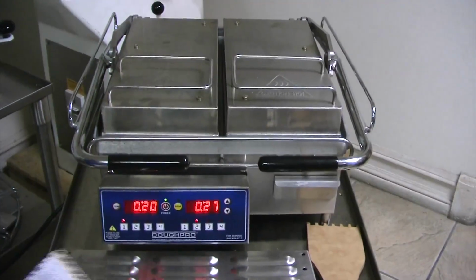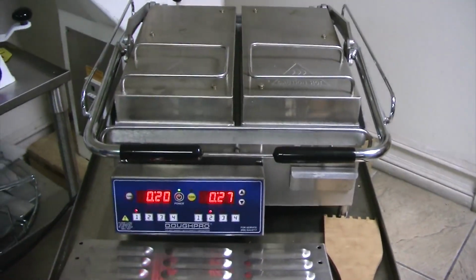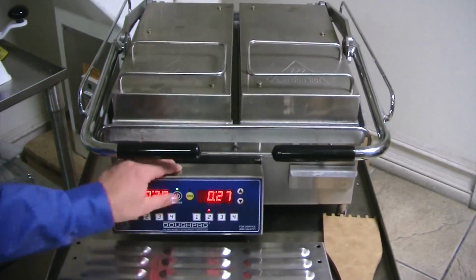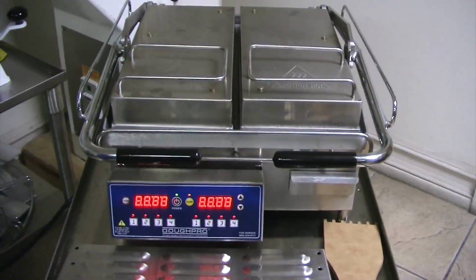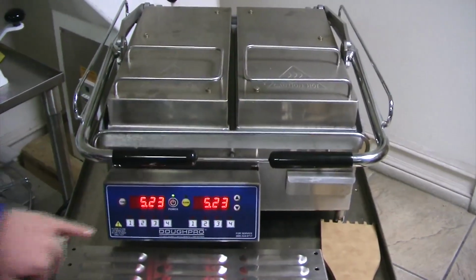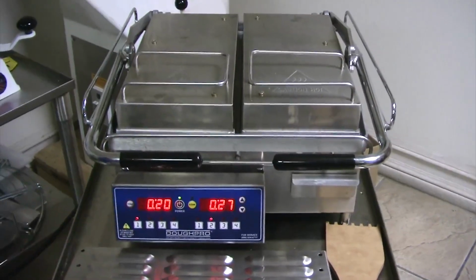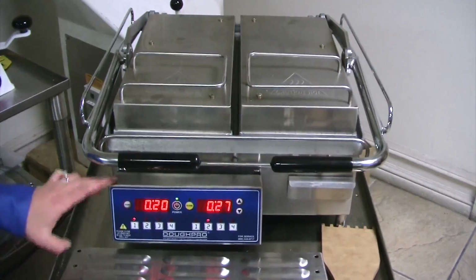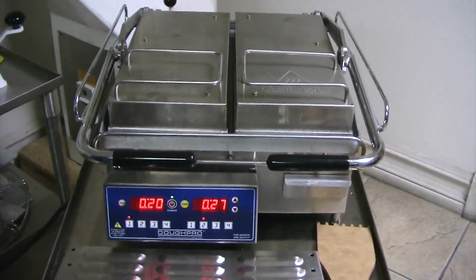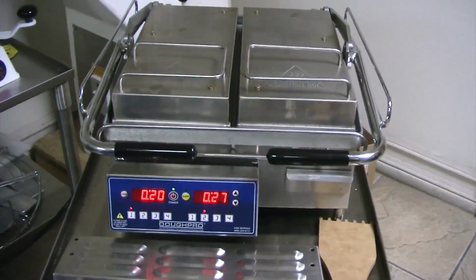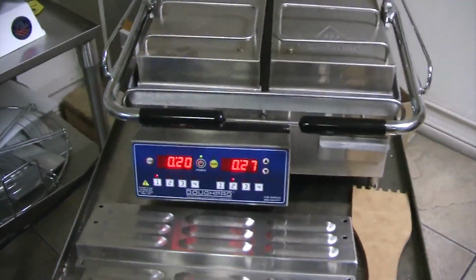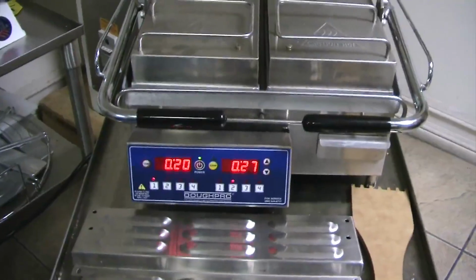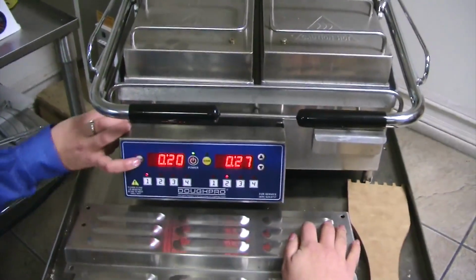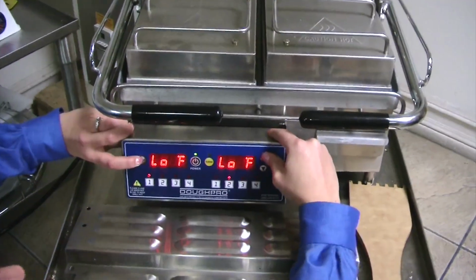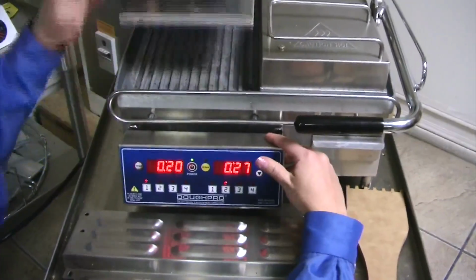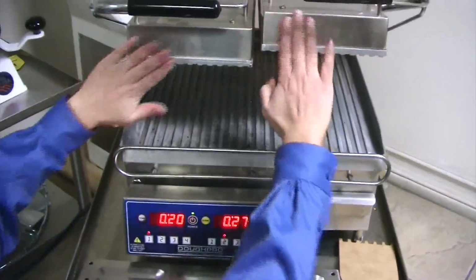This is the control. It will flash red LED when you turn it on, like that. It will say 5.23, and that's just telling you the revision of the microchip in the back of the control. The first thing you need to do when first starting to operate on the machine is hit the temp button and the up arrow, and that'll give you the temperature reading for the left and the right upper grills.